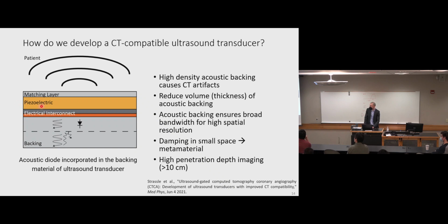You can see we have the piezoelectric material here. This is, for example, like PZT, lead zirconate titanate. This thing will vibrate, and when it vibrates, it produces acoustic waves in both directions. So there's one going out the top, and in this design, in this organization, I'm assuming the patient is on the top. Then we'll have some reflections that go from the patient back into the piezoelectric material of the transducer, and that's what we use to form our image. Then we also have some wave that is going into the back, and we have this acoustic backing down here.